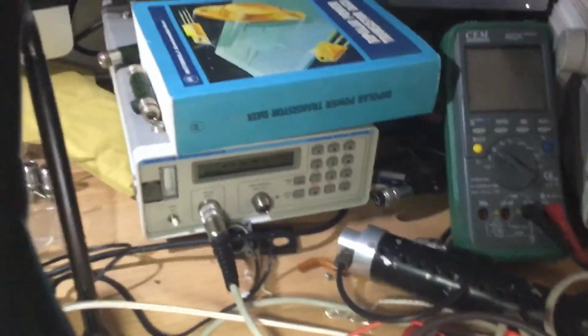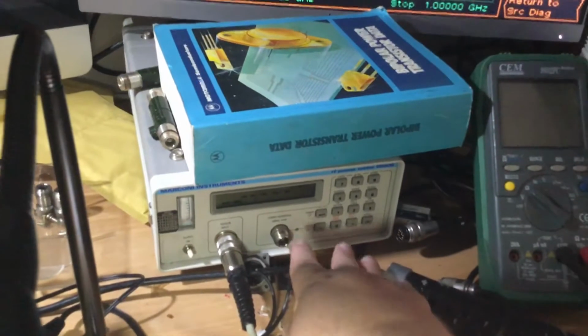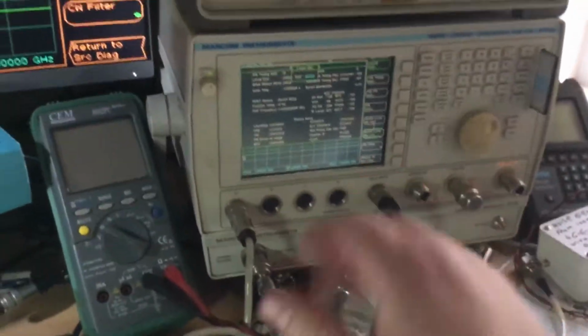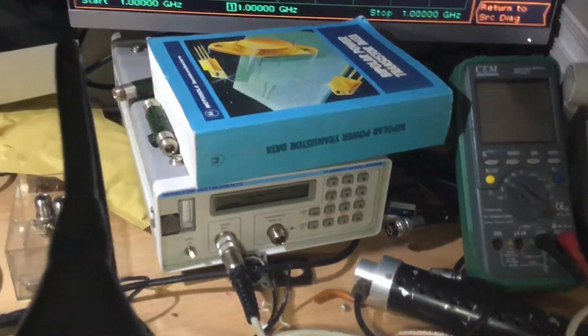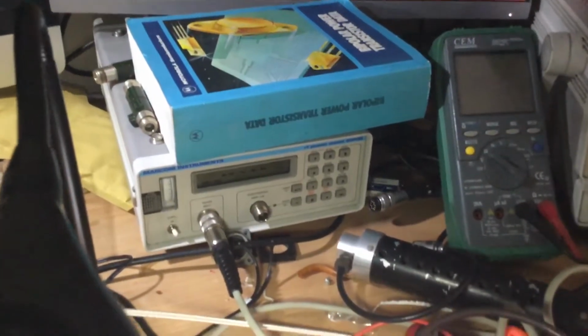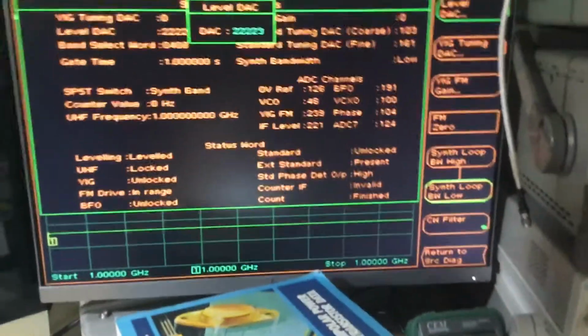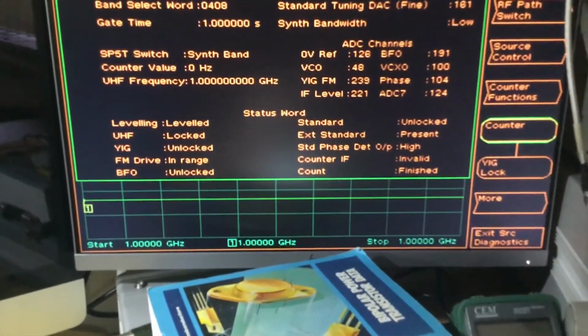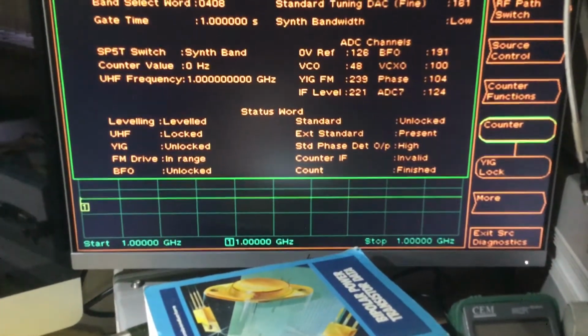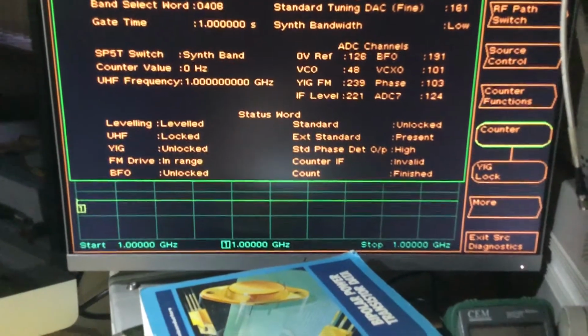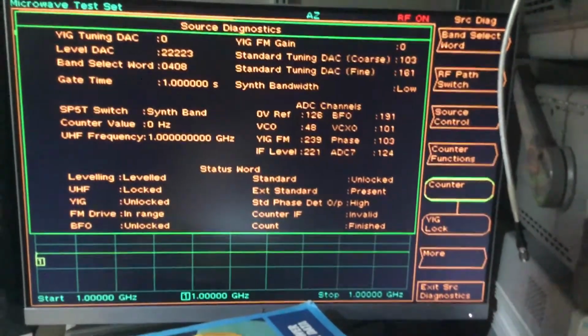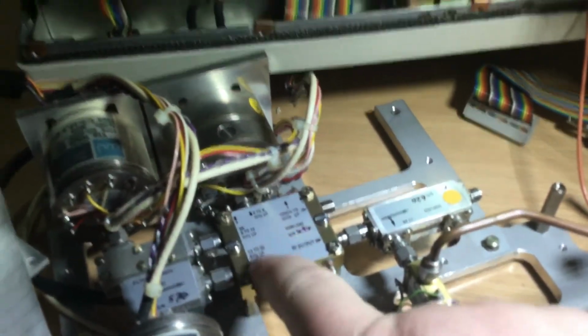So that's a lesson in microwave measurements generally across all radio test sets, be it using a power sensor like this. It has its own calibration features, a Marconi, a Hewlett-Packard, Rohde & Schwarz, they all have the same model where you have to calibrate the sensors before you can use them. As well as that, we've got band select mode. We can select it, we can test the pin diode switch here on this menu, which is in the top right hand corner of the display, and that deals primarily with this switch here for the band select. And then on top of that we have other functions as well.